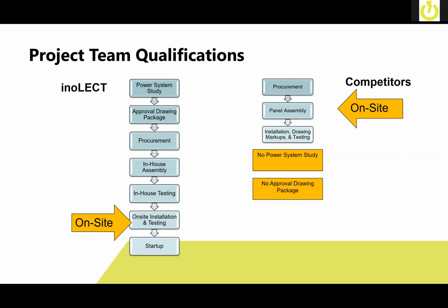What we typically see a lot of times whenever people just call out of the blue and ask for a protection retrofit, a lot of places they'll do procurement, they'll immediately get started without looking at what is needed to maybe enhance your system or provide you additional benefits. They'll move to panel assembly, and then while they're on site, they're actually doing the panel assembly. They bring a box of relays with wire and lugs, and they do full assembly on site. And that's their first time looking at drawings and performing markups and testing. A lot of times we don't see a power system study being done to make sure you meet your needs in arc flash incident energy reduction possibly, or an approval drawing package where you get a chance to take a look at the system, take a look at the nameplates, the test switch layout, et cetera, and make sure that it meets your needs.